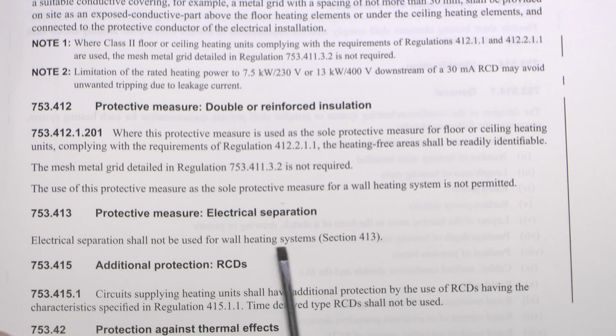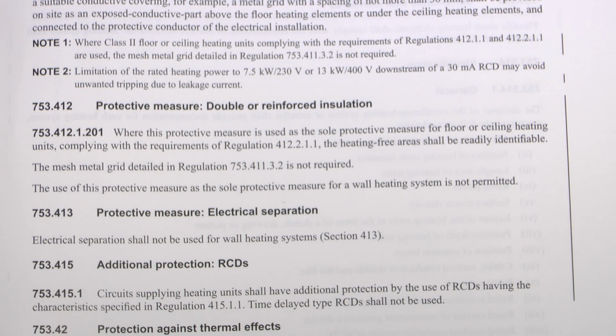This one here, 753413, protective measure of electrical separation. Electrical separation shall not be used for wall heating systems. Previously this had a different number and it basically prohibited it for all items, so now it's only prohibited for wall heating. 753415-1, again additional protection with RCDs. This has been amended, and the difference now is that time delayed type RCDs shall not be used. Previously obviously they could be, so those are no longer permitted.